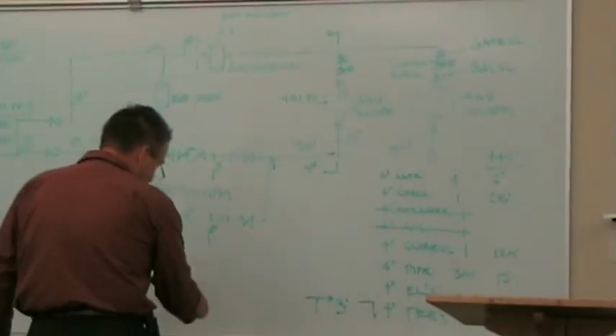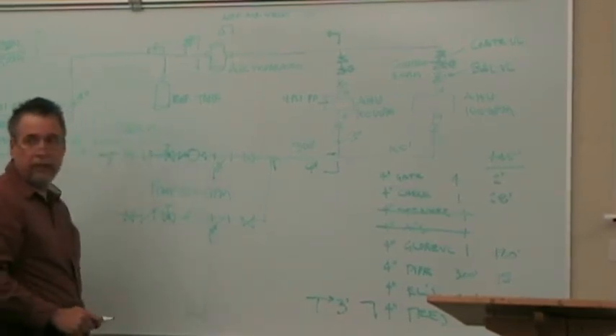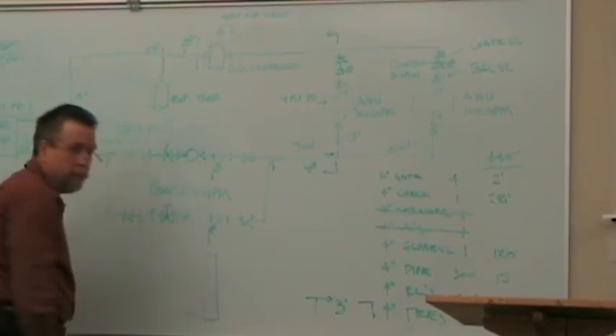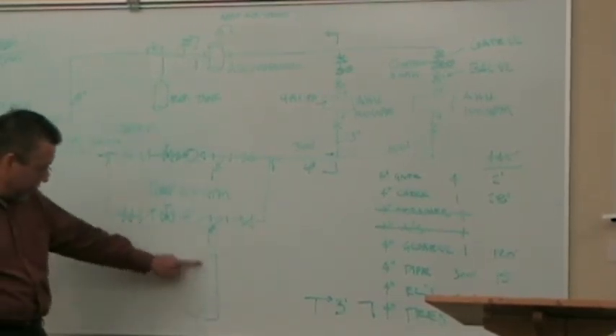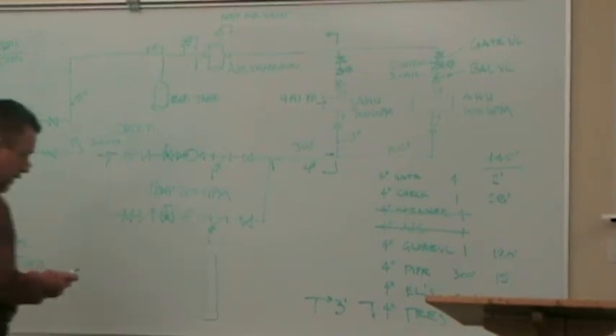Now, this is a closed piping system, meaning that if I'm on the ground floor, I have to pump up to the top of the building, a 10-story building, and I come right back down. It's a closed piping system. I got just as much head going up as I do going down, so I don't add any head to my pump. Now let's compare that to a cooling tower.